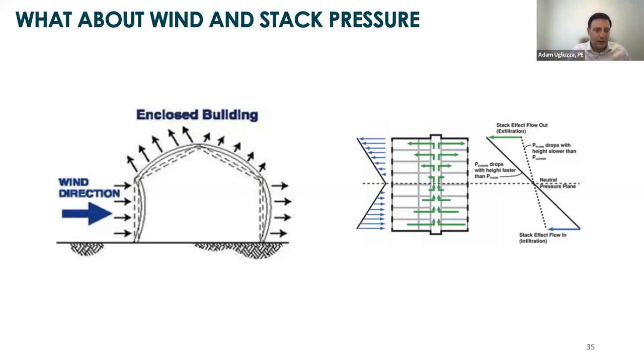And then wind, commonly, if you plan this test out three weeks in advance, you're not going to be able to predict whether there's going to be wind the day of the test. So you can handle that on the day of the test. It's just how you're setting the equipment up. You can add more pressure ports at the bottom and average out the impact of the wind. There are ways that an experienced testing agency can handle wind. If it gets really, really bad, you might just have to postpone a test. But generally, if your wind speeds are under 20 miles an hour, you can get through it. It might take a little bit longer, but there are ways to get through it and get accurate results.